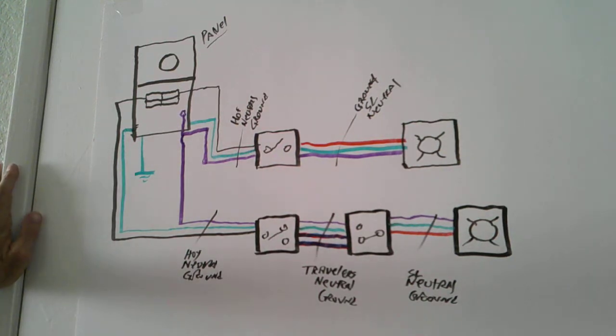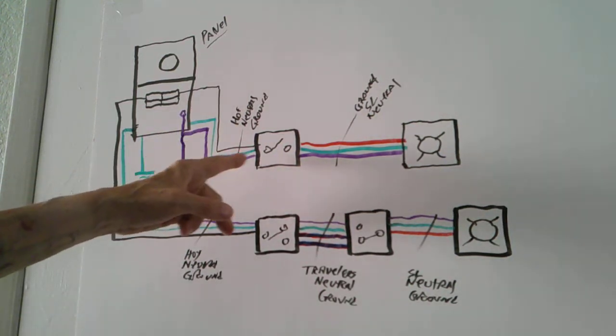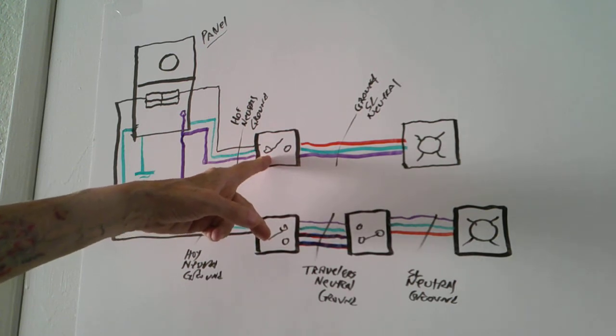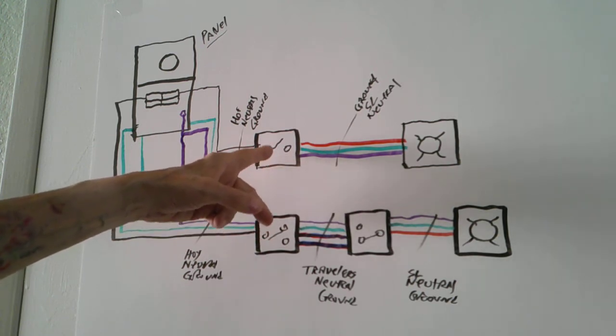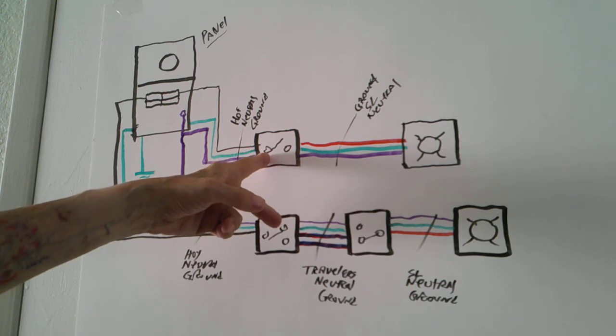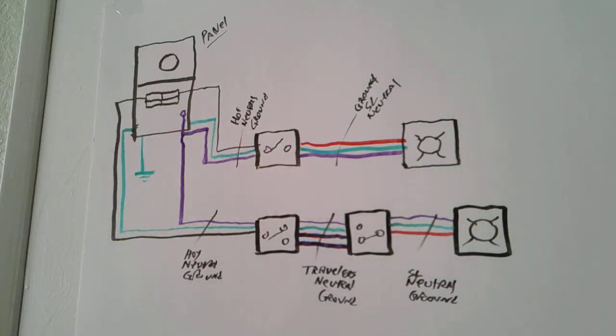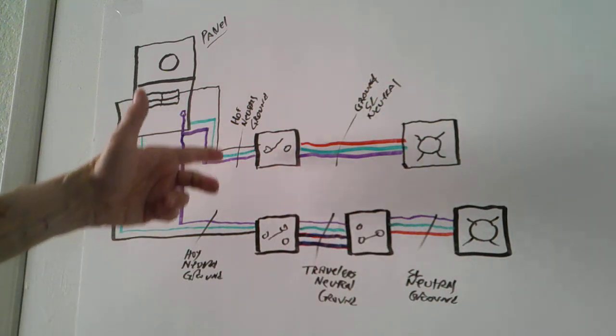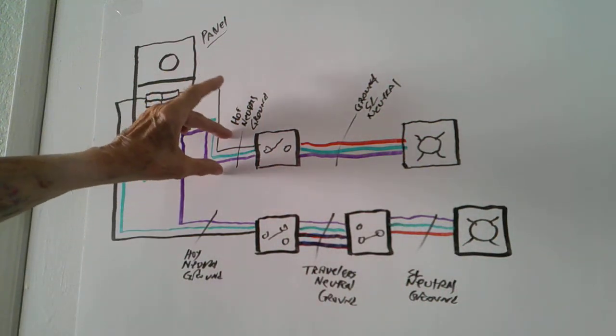The next step would be to check this group of wires here going to the switch. So what you would want to do is confirm that you have a hot line going to the switch, and you can either test that from the ground or the neutral to the hot wire going to that switch. Now, in the event that you have no power here, then there's a problem with this group of wires.